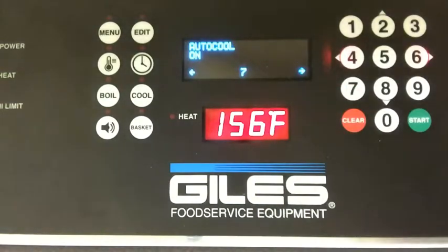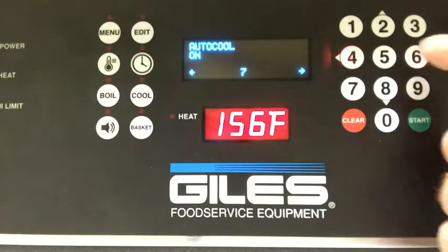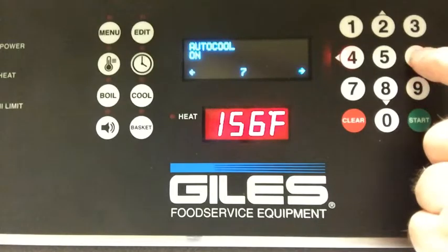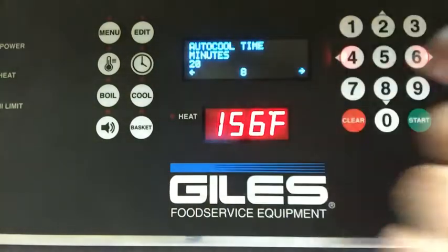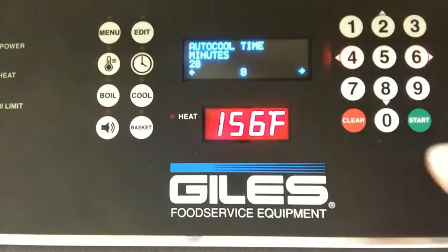Auto cool. That's this pressing of this cool button. This one's set so that it will automatically go into that cool mode if it has not been used for a predetermined amount of minutes, and that is 20 minutes. So this can be changed. You can run this on up to 30 minutes. I think you can go as high as like 60 minutes. And if you want to do that, then you certainly can.